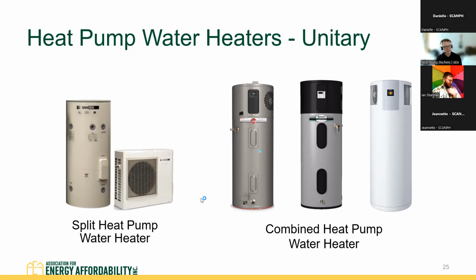If the closet this is in has this thing pumping out cold air — even if outside it's like 48 degrees, this thing is pumping out 30-35 degree air — it's going to cool down the closet that it's in. So it might generate much colder ambient conditions for itself, causing it to go into resistance mode and spike the electrical usage of the equipment, if you don't deal with the cold air coming out of the heat pump.